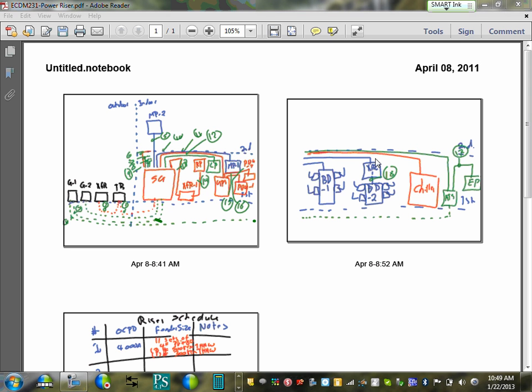Just remember when you're designing this that we're going to have two breakers on Gen 1. One that feeds the gear, and then a smaller one that's going to feed your ATS for your emergency. And those two breakers would have to be in separate enclosures. Okay, because code does say... can I write again? I think you can write again.